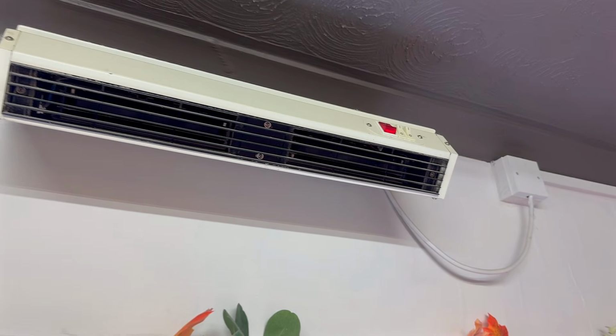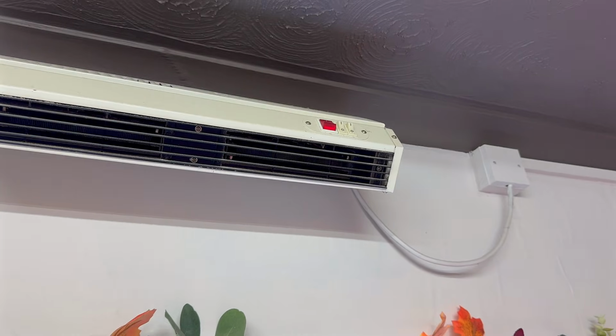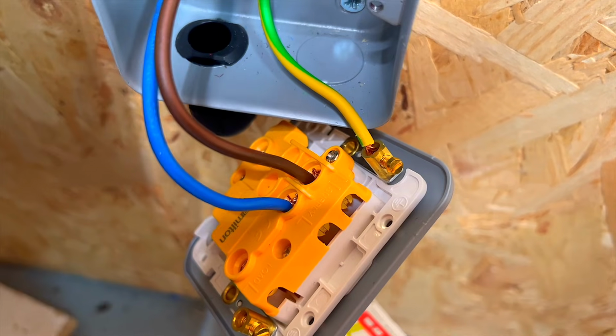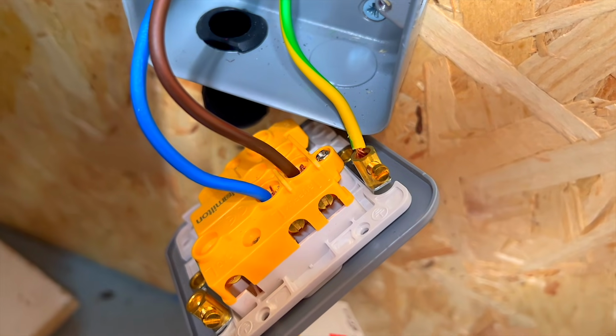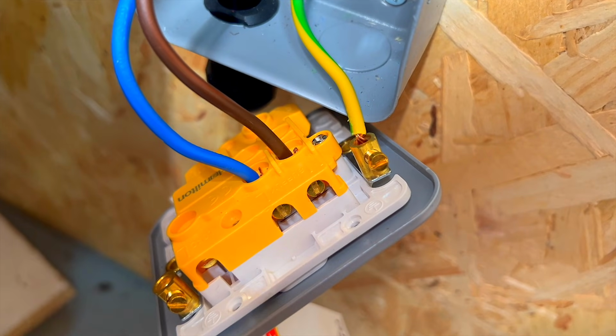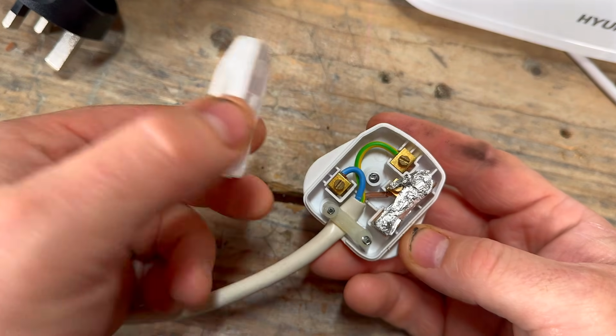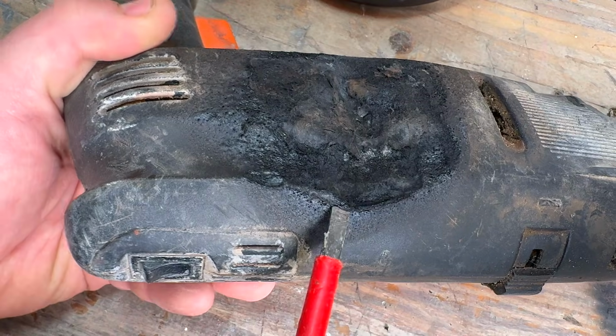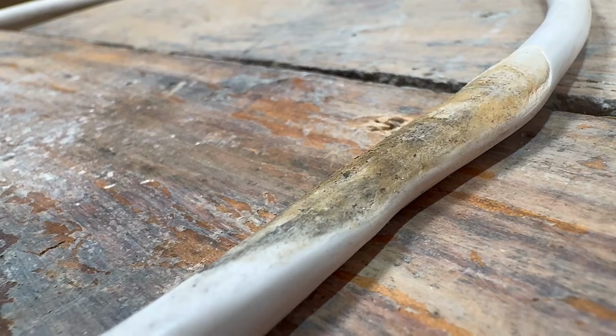Where equipment is permanently connected, competence must also extend to safe isolation. Anyone disconnecting or reconnecting equipment must be trained and experienced in the safe isolation procedures. This is critical because safe isolation carried out incorrectly raises a huge risk to the operative. Competence means that the operative can make an informed judgment about the safety of the piece of equipment that's going to be tested. That is the competence required by law and the competence expected by the Code of Practice.